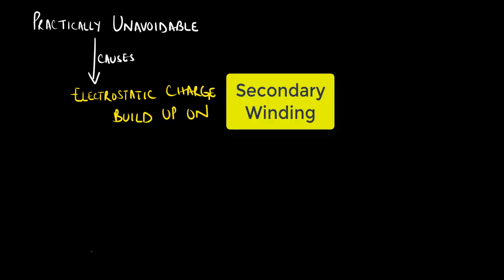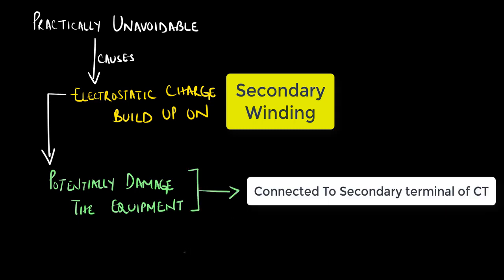They are practically unavoidable, and they cause an electrostatic charge to build up on the secondary winding, which causes high secondary voltages and can become extremely dangerous for electrical workers. Furthermore, it can potentially damage the equipment connected to the secondary terminals of the current transformer. It is for these reasons why grounding a current transformer is highly recommended.